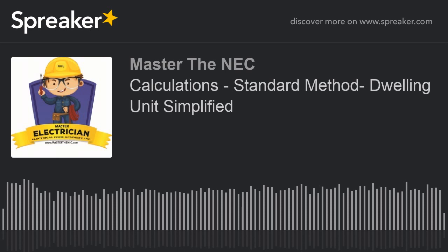The next one, and again, we're following down the list. We're simply going down now to 220.55. We're going to deal with the cooking. And in our case, we had what? We had a range at 12 kW. Okay. Well, the range, oven, cooktops, and other household cooking appliances over 1 3/4 kW fall under 220.55. In our case, we had a 12 kW range.